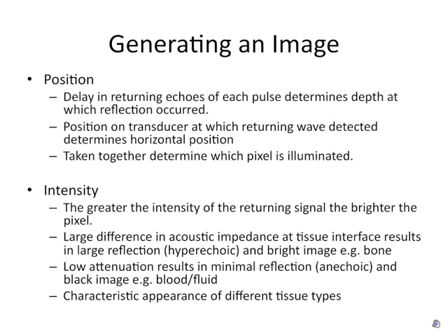The image is generated by lighting pixels on the screen correlating to the reflected ultrasound waves. The position of the pixel illuminated is determined by the position on the transducer at which the returning beam is detected, and by the delay in return of the ultrasound energy, hence determining horizontal position and depth. The brightness of each pixel is determined by the amplitude, or energy, of the returning ultrasound wave.